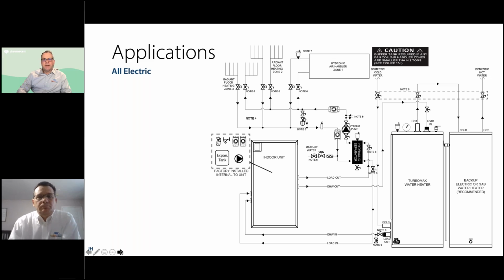This is just a quick piping diagram. This is one of the ones that are in the installation manual. And you can see here towards the middle of that diagram, we're showing a hydraulic separator. We don't need a buffer tank if we have an air handler that is around 2 tons or larger.